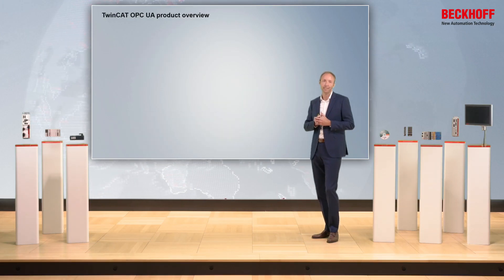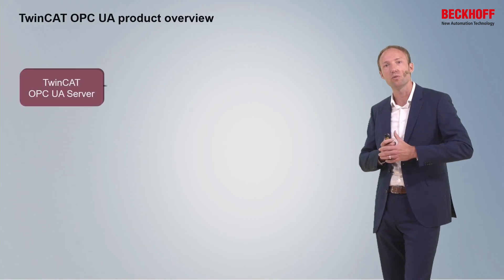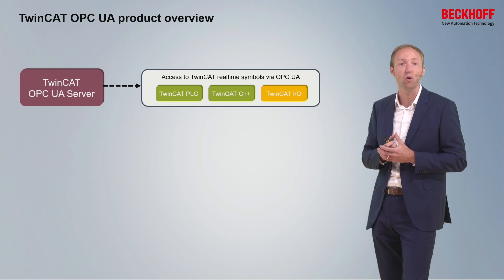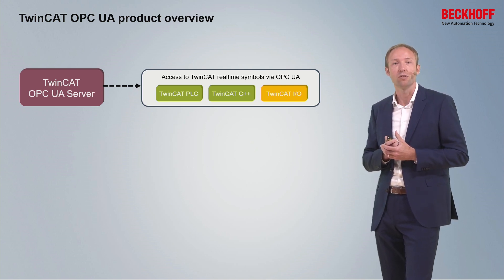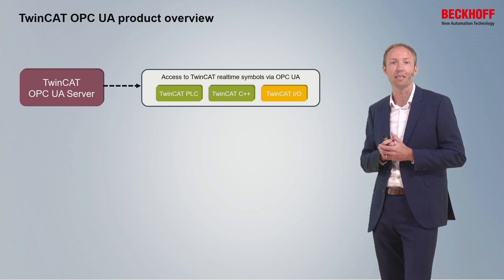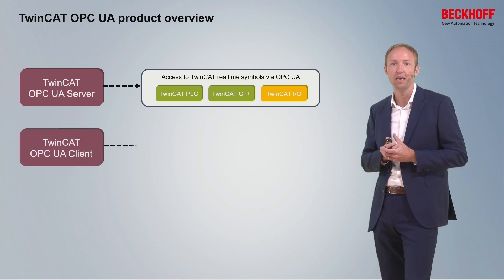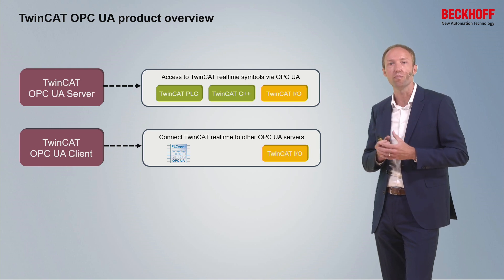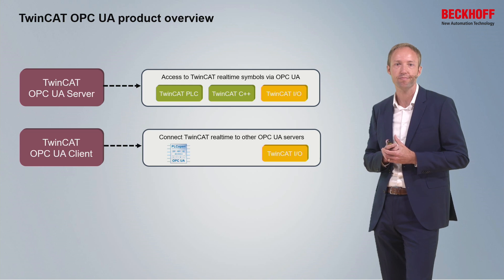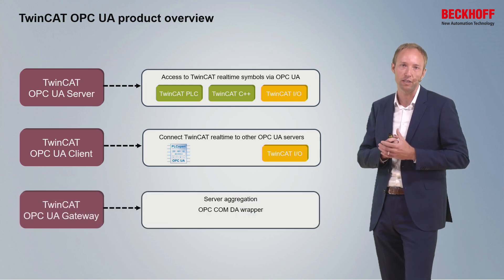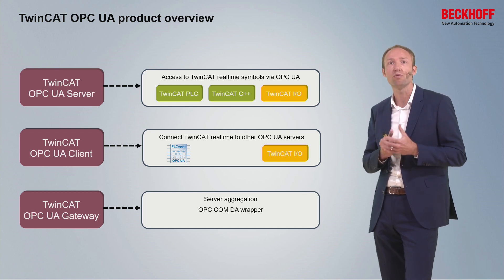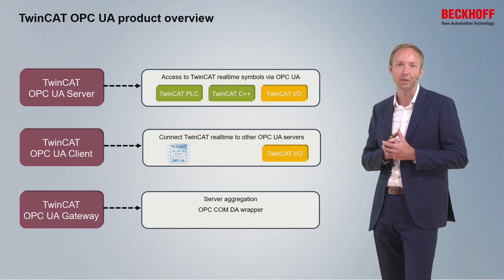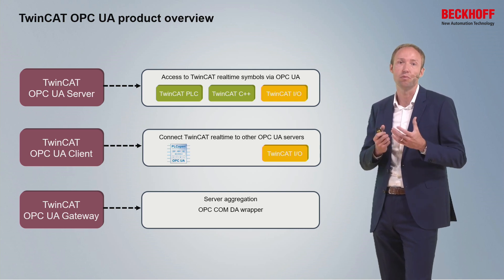There are three major components inside TwinCAT OPC UA. The TwinCAT OPC UA server provides access to symbols from the TwinCAT Realtime — simple variables, data structures, or methods callable by an OPC UA client. The TwinCAT OPC UA client lets you access other OPC UA servers to read/write variables or call methods, available as PLC open function blocks or an easy-to-configure I/O device. The TwinCAT OPC UA gateway wraps the server, provides a free-of-charge OPC COM DA interface, and lets you aggregate multiple TwinCAT OPC UA servers.